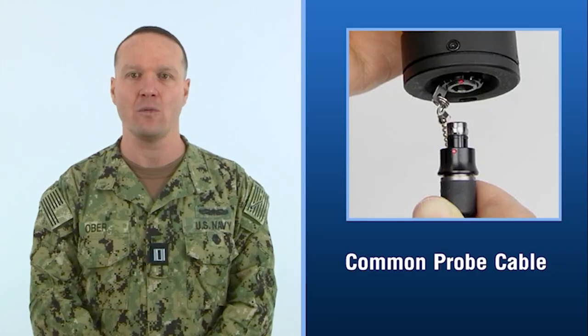The common probe cable, which connects base unit to probes, carries only low voltages. This feature allows use of common probe cables of varying lengths without needing to recalibrate and enhances reliability. The operator does not need to adjust high voltage settings when switching between available probes. The probe can be hot swapped, meaning the common probe cable can be connected or disconnected without having to power down the base unit. RDS equipment utilizes Geiger-Müller or GM technology, scintillation, photomultiplier tubes, and solid-state semiconductor-based technology to detect the various forms of radiation.